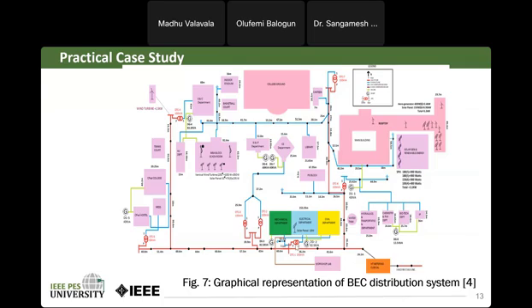The IFC meter includes a digital meter from a company that can access data from the transformer, which is essentially load data. We also have an IO internet module that communicates with the nearby department through two IP links, using an assigned internet protocol address to transfer the complete consumption data into the SCADA room.